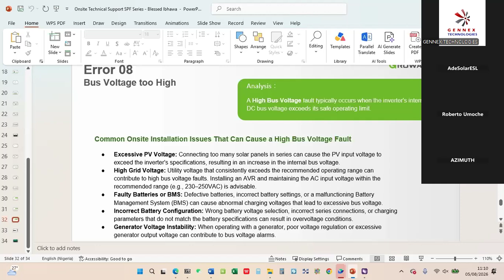This leads to abnormal voltage, causing the inverter's voltage to exceed a particular threshold. This can come from the PV side or the grid side, because the way the machine works, there's a central bus voltage point where voltage from PV, grid, and battery all meet. That's why the inverter can start with PV, grid, or battery - because of that central bus. So if one of those sources is too high, the inverter will report error 08. Most times we need to check your PV - if it's too high, maybe in the morning the voltage rises, so please ensure you make the adjustment.